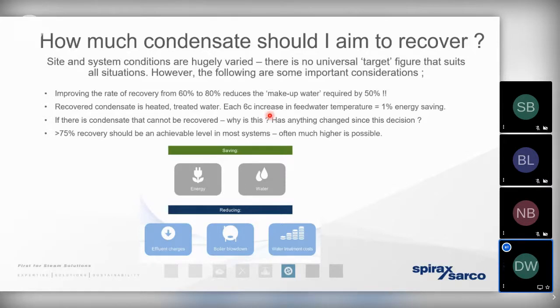And we also know that that condensate is not only water, it's not only heat energy, but it's also been chemically conditioned already. So we've got a further saving with the chemical costs. So I want you to remember a rule of thumb here, and that's that we want to be aiming to recover ideally 80% of the steam that we're generating in the form of condensate. And we want to keep the temperature of the hot well at approximately 80 degrees, maybe even 85 degrees. So please remember that rule of thumb. That gives us an indication that we're going to have a well-designed steam distribution network and a healthy rate of condensate recovery.